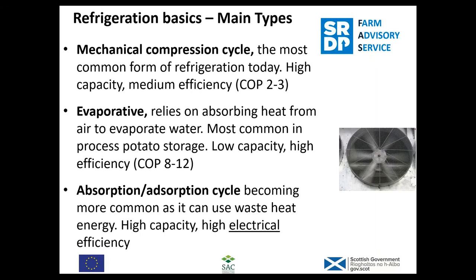Main types. There are lots of types of refrigeration plant. The one that we all know is the mechanical compression cycle — that's in pretty much 90–95% of refrigeration equipment. It's high capacity and medium efficiency. When I say efficiency here, I'm really talking about electrical efficiency. Then evaporative cooling: that just relies on absorbing heat from the air to evaporate water. This is found in agriculture quite a lot for processed potato storage — also called adiabatic cooling. It's quite low capacity; you can't go down to low temperatures. But it's very high electrical efficiency — it's just the efficiency of the fan.